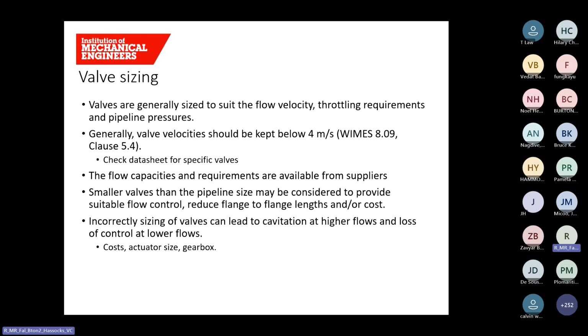I'm now going to talk about valve sizing. Valves are normally sized based on the flow velocity, the throttling requirements, or the pipeline pressures. We generally keep to below 4 meters per second velocity, but often much less than that, around 2 to 2.5 meters per second. It's always important to check with the manufacturer, though, to make sure that the velocities you're proposing are suited to the valve.